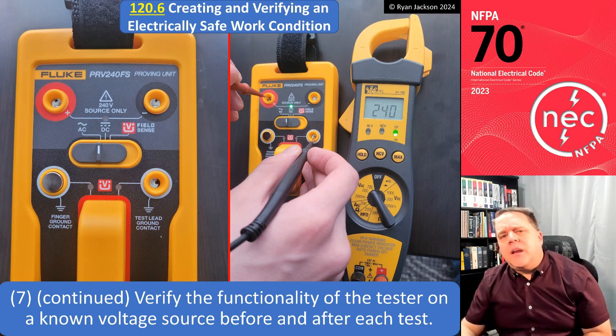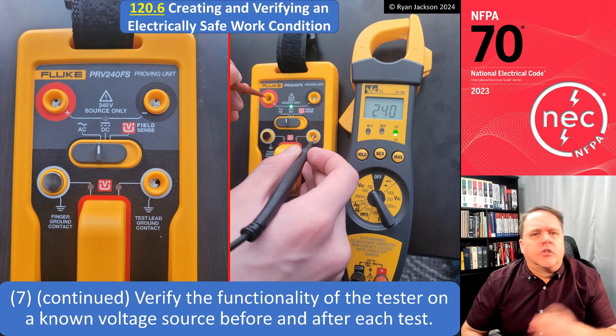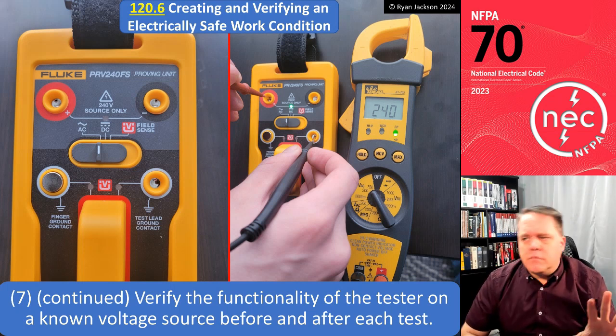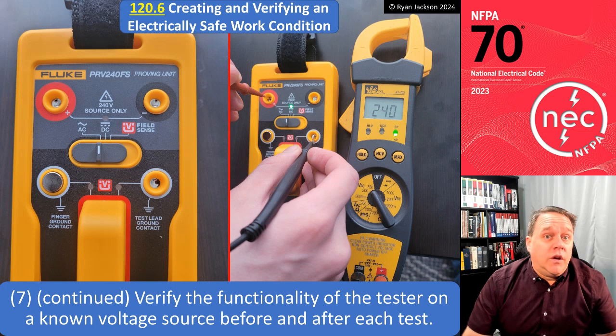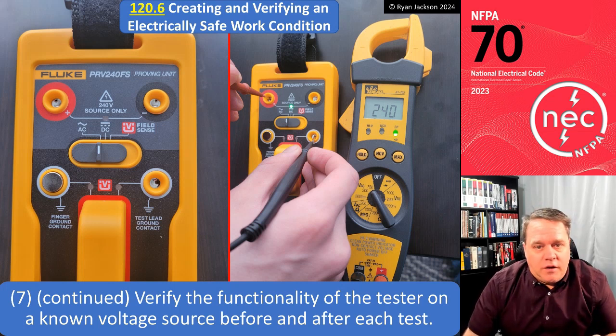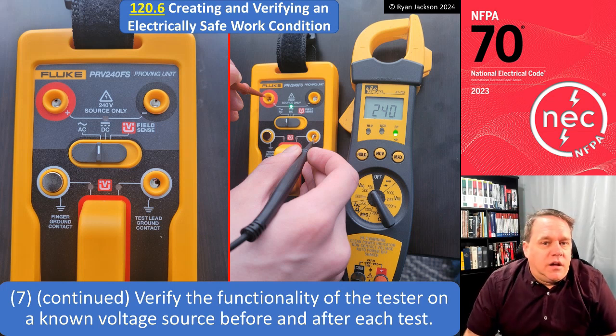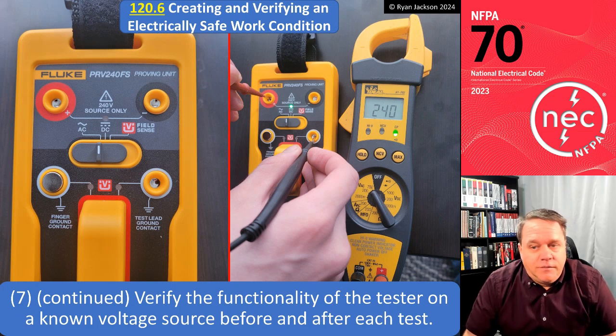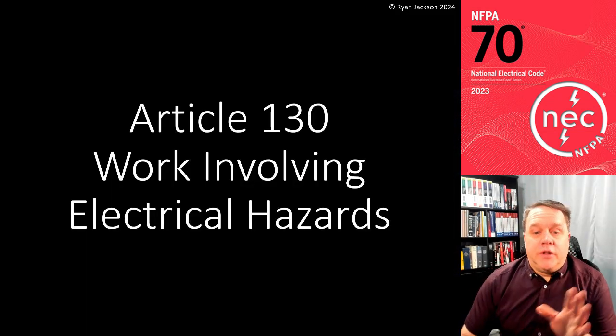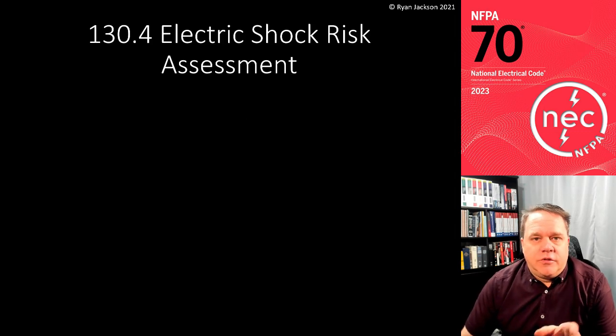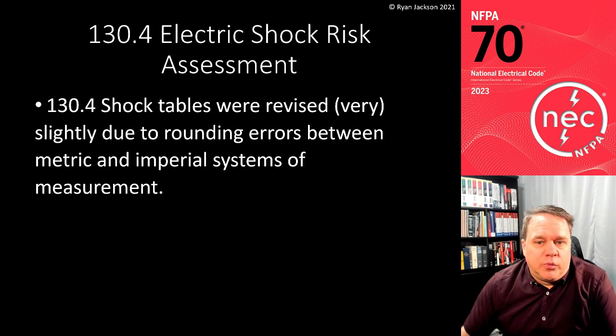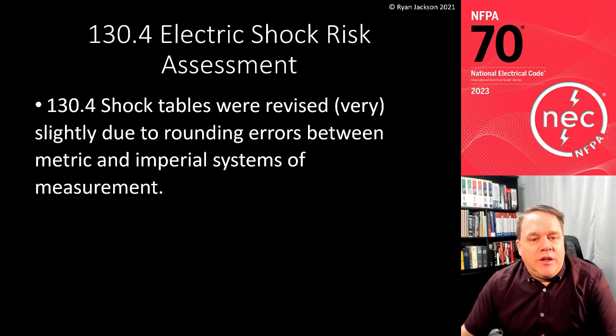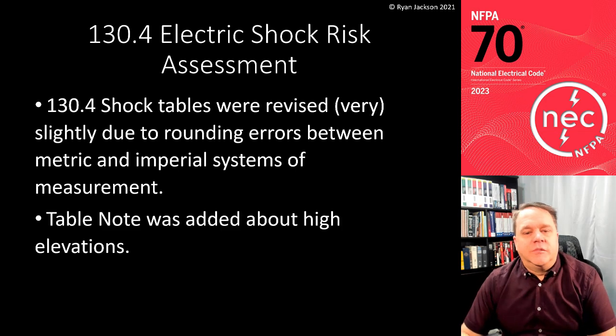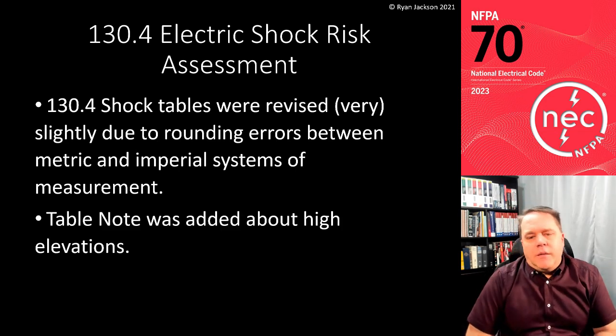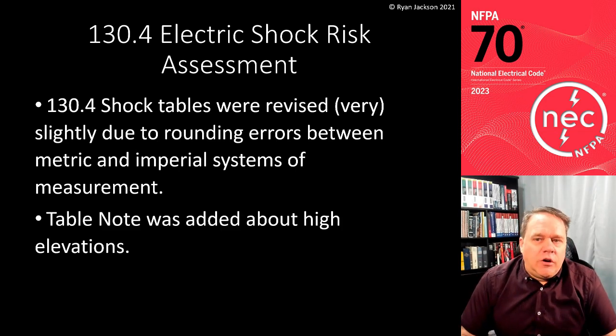Item 8 talks about grounding circuit parts when needed. Not often that comes up, but when it's necessary, we do need to do it as well. So there are 8 parts to creating and verifying an electrically safe work condition. All right, Article 130, work involving electrical hazards. 130.4, the electric shock risk assessment. The shock tables were revised very slightly due to rounding errors between metric and imperial systems of measurement, and a table note was added about higher elevations.